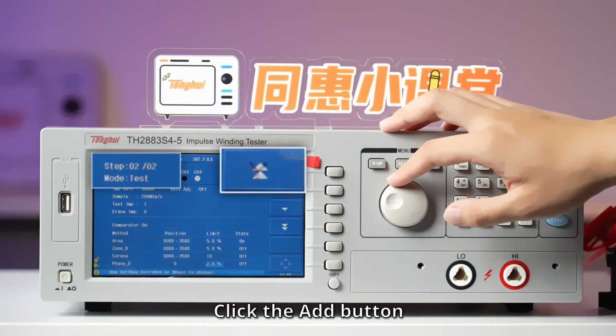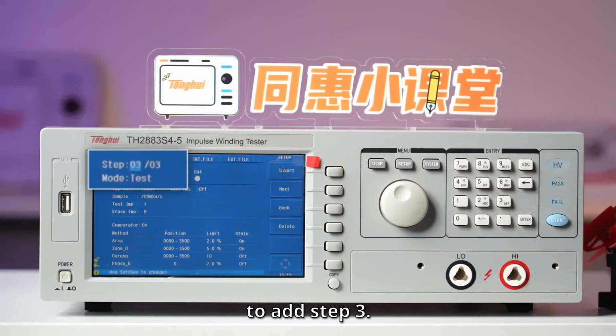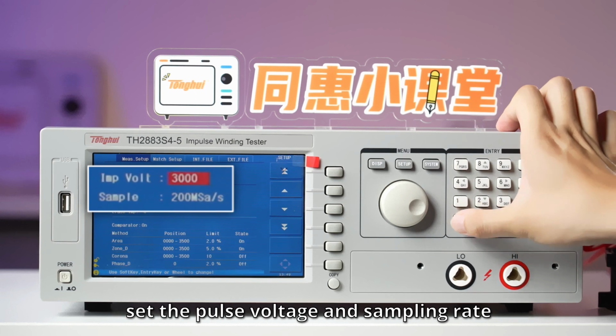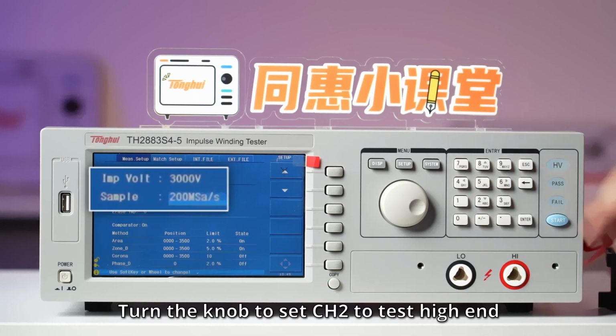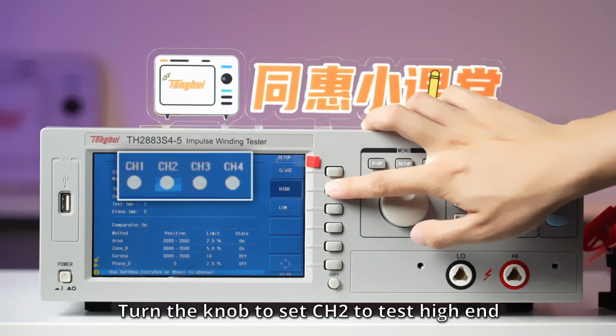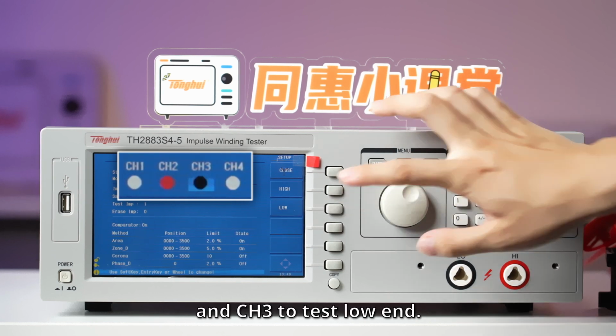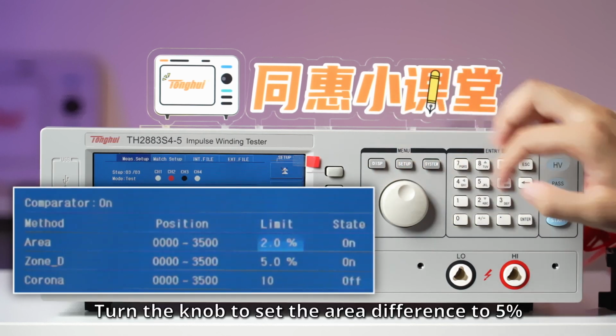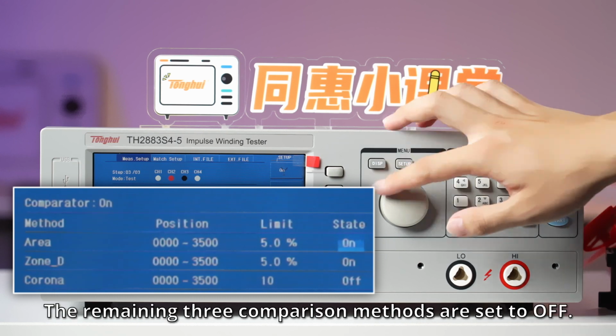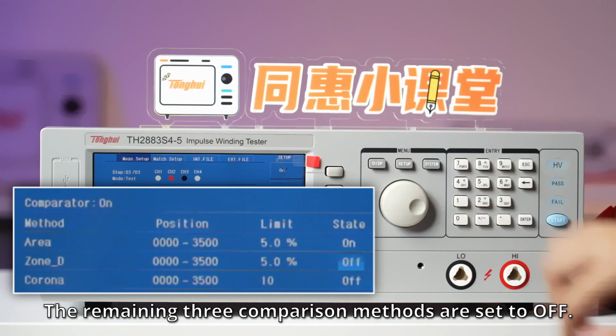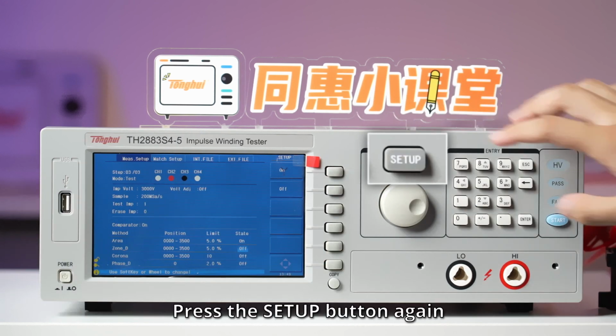Click the Add button on the right side of screen to add Step 3. Set the pulse voltage and sampling rate. Turn the knob to set Channel 2 to test high end and Channel 3 to test low end. Turn the knob to set the area difference to 5%. The remaining 3 comparison methods are set to off. Press the Setup button again.